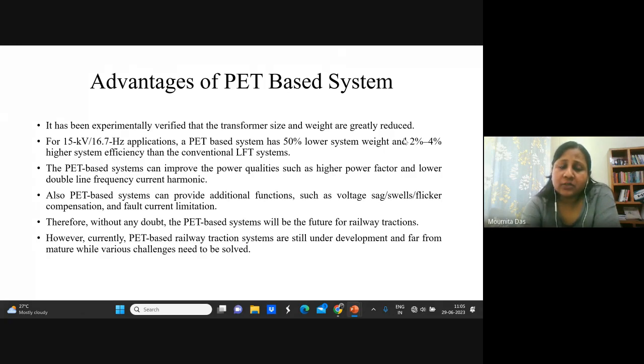For a 15 kilovolt, 16.7 hertz application, the power electronics transformer based system may have 50% lower system weight and 2 to 4% higher system efficiency than a line frequency transformer. The efficiency gain may not look very high at 2 to 4%, but in terms of size, it's half the weight of the line frequency transformer, so there's a huge advantage.